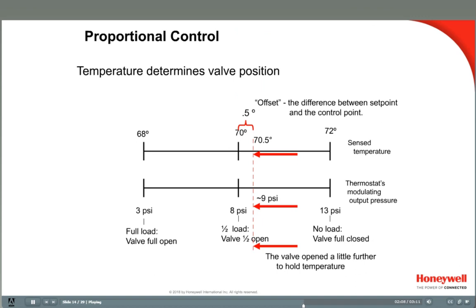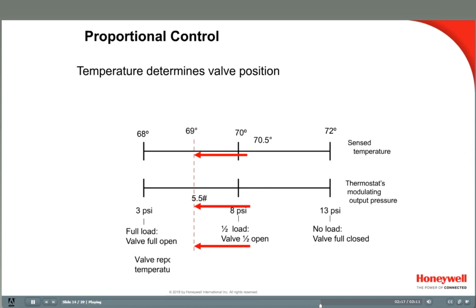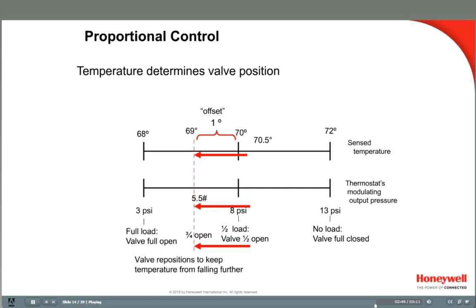If the heating load increases further and the room temperature drops to 69 degrees, the bleed rate will increase, and the branch line pressure will drop to about 5.5 pounds, causing the valve to open to about three-quarters open. This increases the rate of BTU transfer into the room to replace the BTU loss that caused the temperature to fall to 69 degrees. We now have a 1-degree offset. Proportional control matches heat replacement to heat loss and is best for large buildings where temperature changes slowly. With the correct throttling range, the offset seldom gets more than 1 degree above or below set point.